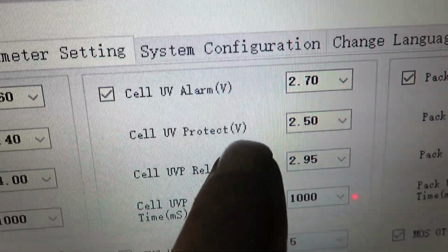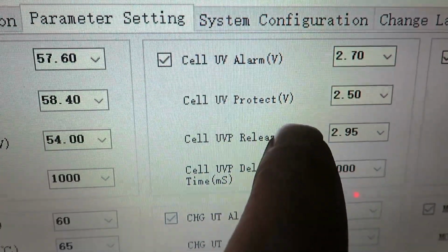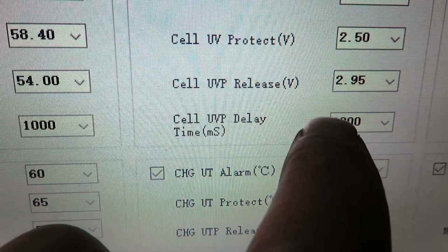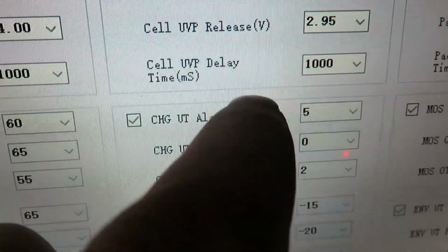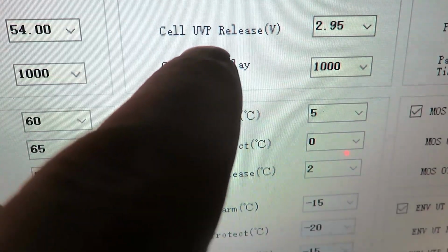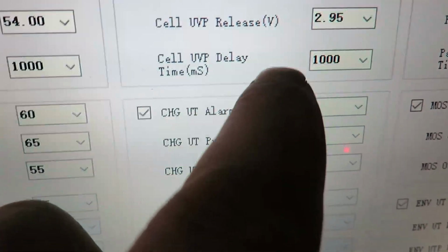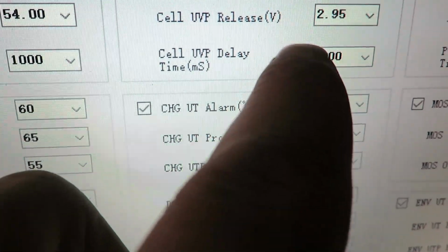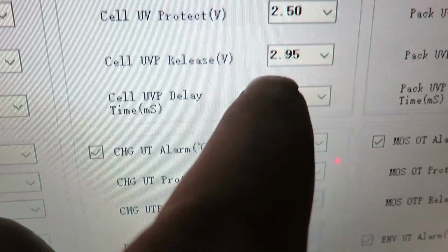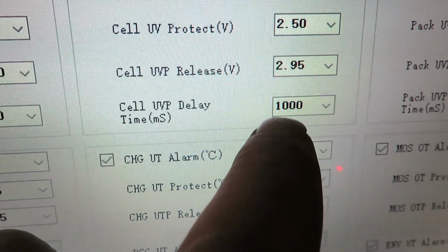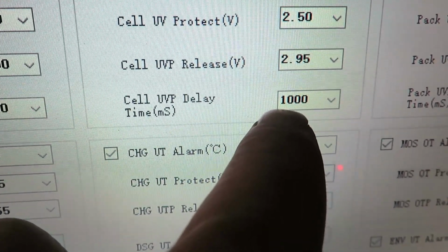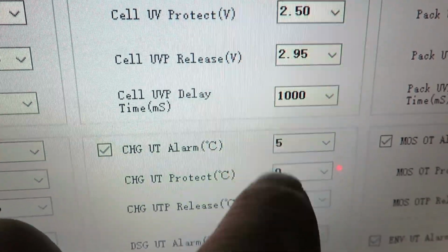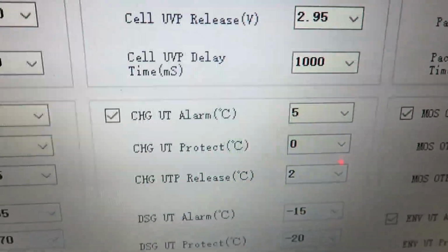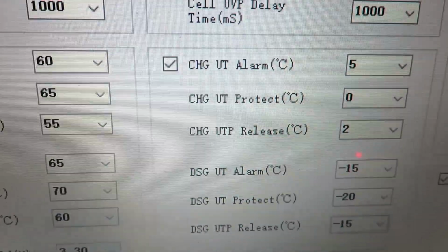Under voltage is set for 2.7 alarm, 2.5 for protecting it, and it'll release when it gets back up to 2.95, with a delay of 1000 milliseconds.